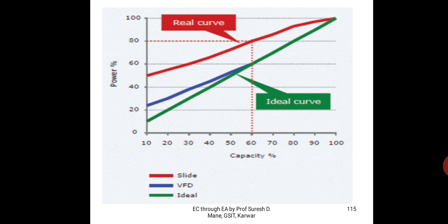For 60% loading, you can see the dotted red line. 60% loading, the power consumed is 80%. So this is not good. For 60% loading, we want only 60% power to be used. So the blue line is the VFD line, variable frequency drive line. You can see here for 60% loading, the power consumed is 60% only.